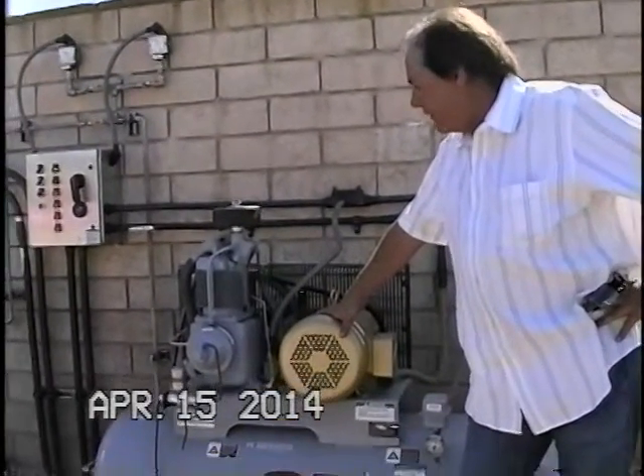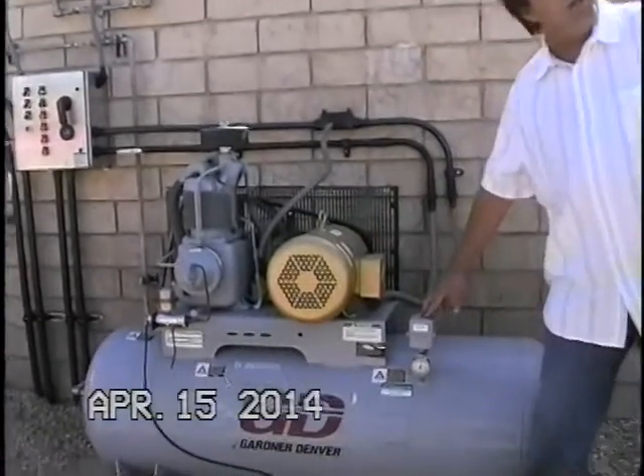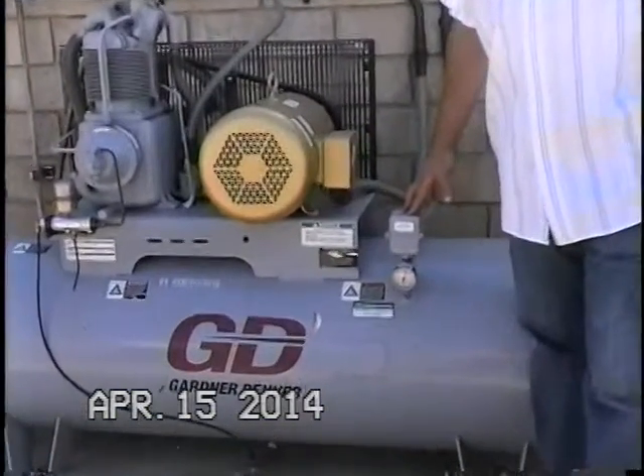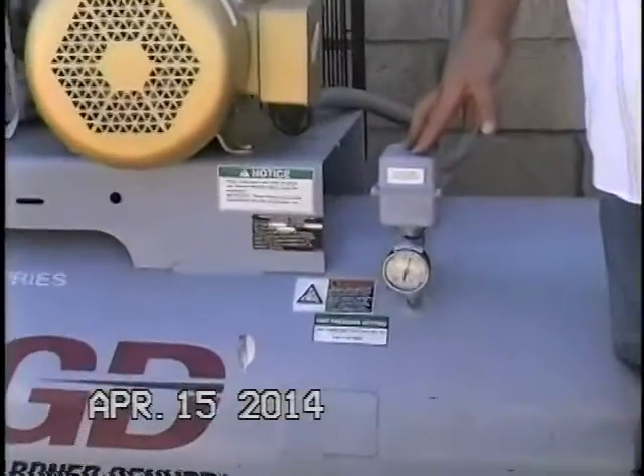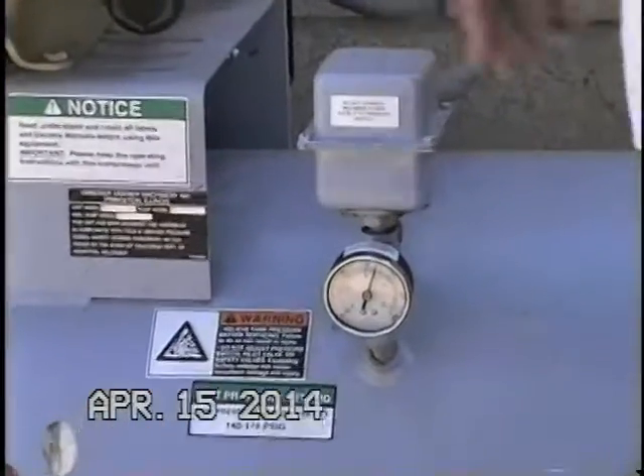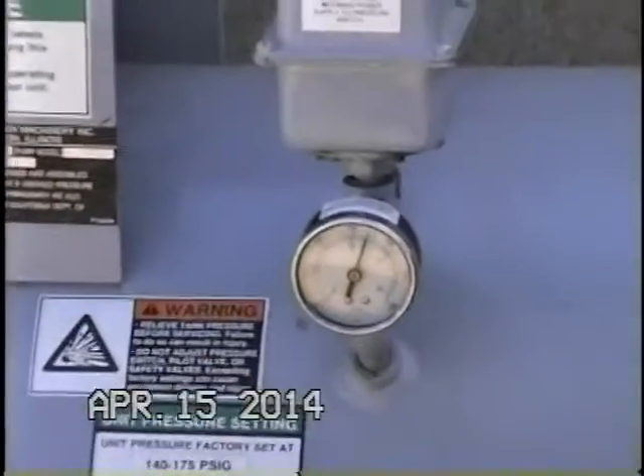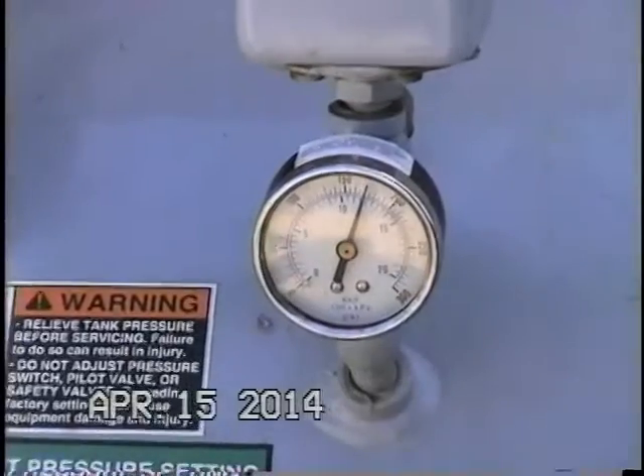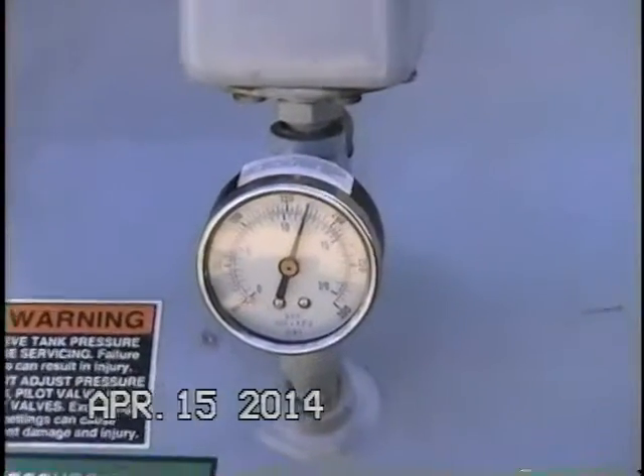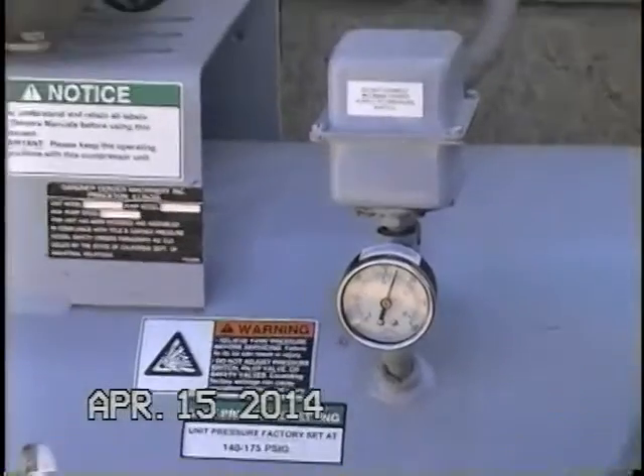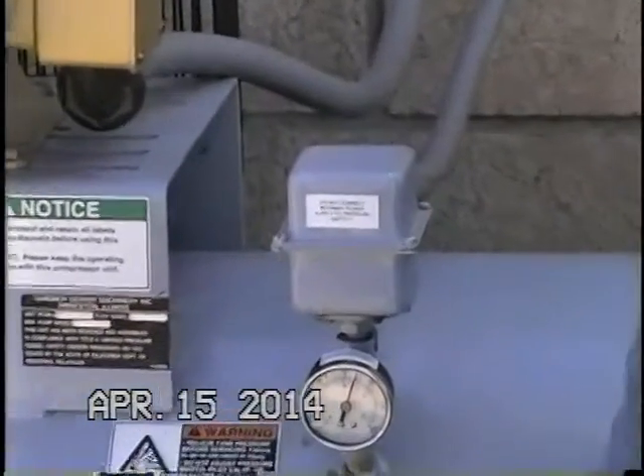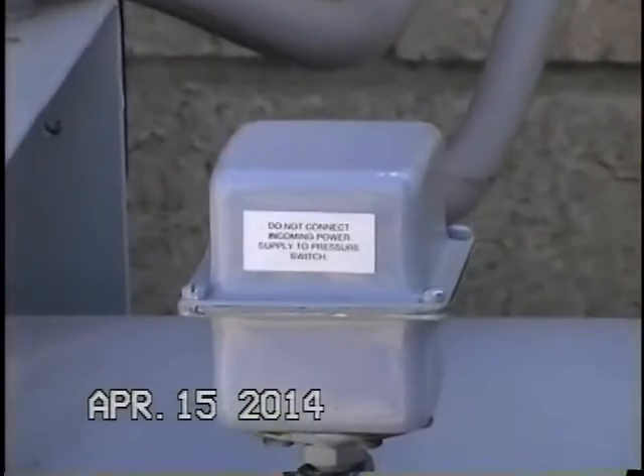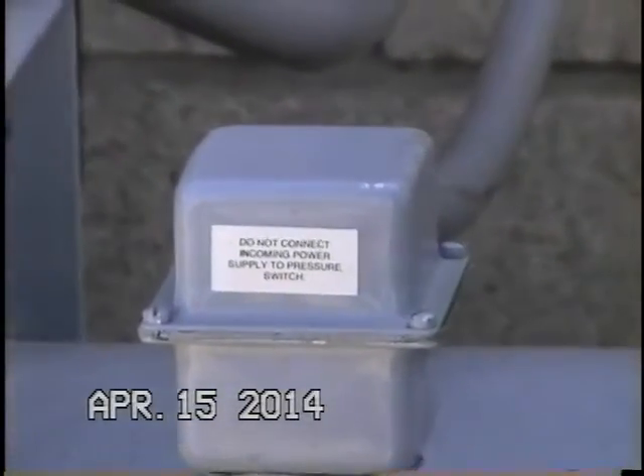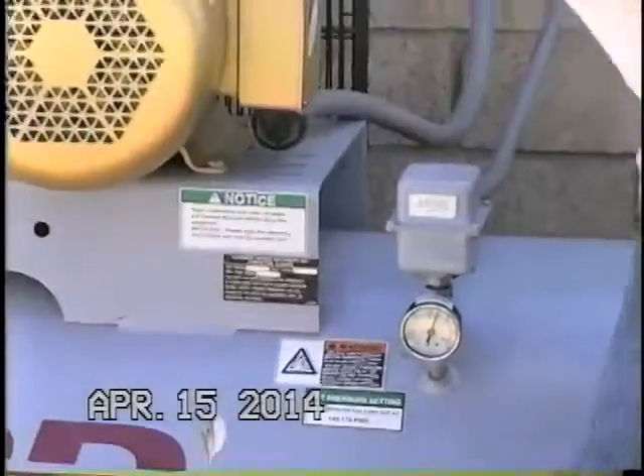They basically have a function of a pressure switch. This pressure switch here is set as an on and off pressure switch. We currently have it set, I believe, at about 150 psi off, and it comes on at about 140, somewhere along that range. I think right now we're at 150, that's 160.